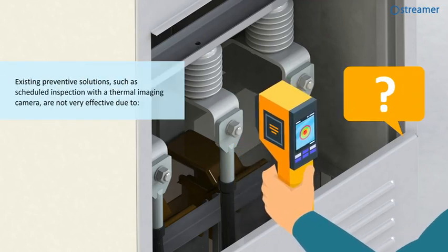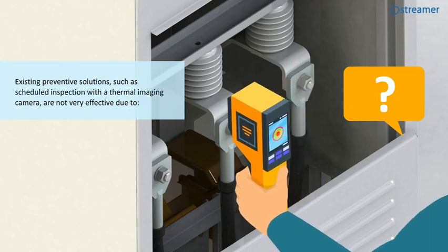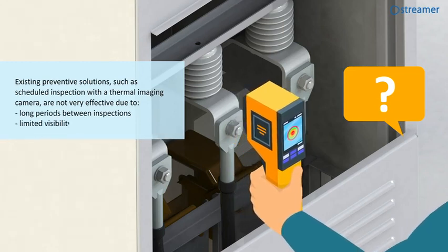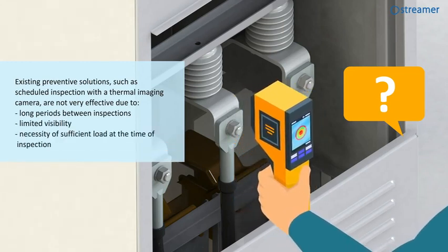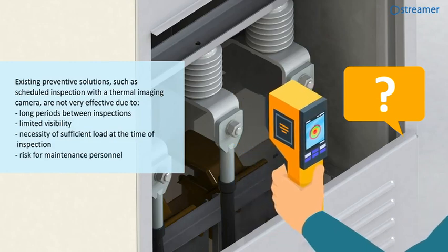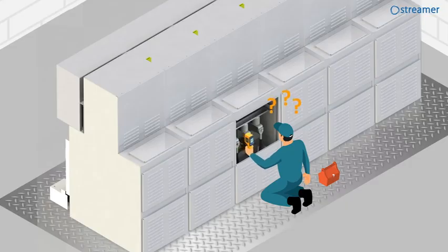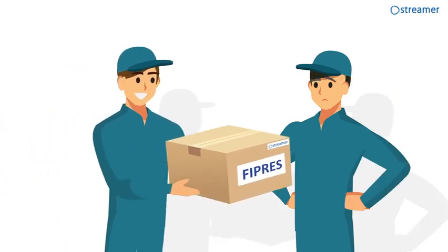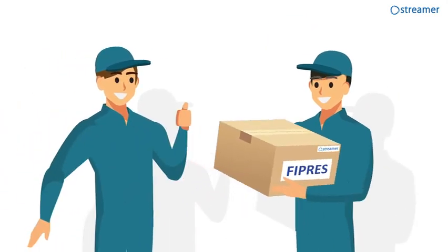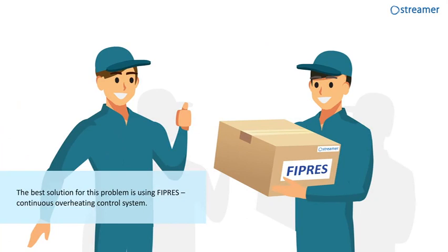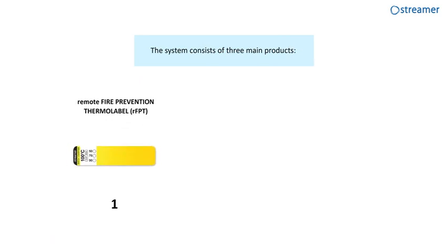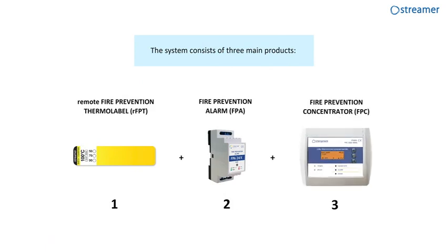Existing preventive solutions, such as scheduled inspection with a thermal imaging camera, are not very effective due to long periods between inspections, limited visibility, necessity of sufficient load at the time of inspection, and risk for maintenance personnel. The best solution for this problem is using FIPRES, Continuous Overheating Control System. The system consists of three main products: Remote Fire Prevention Thermal Label, RFPT, Fire Prevention Alarm, FPA, and Fire Prevention Concentrator, FPC.